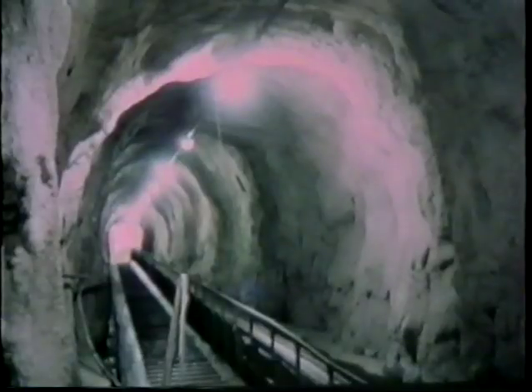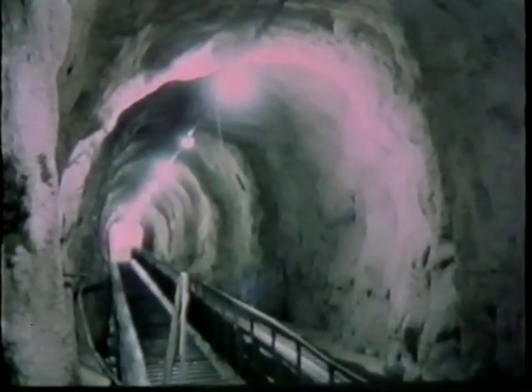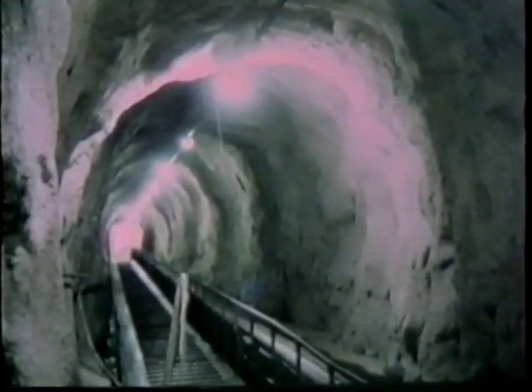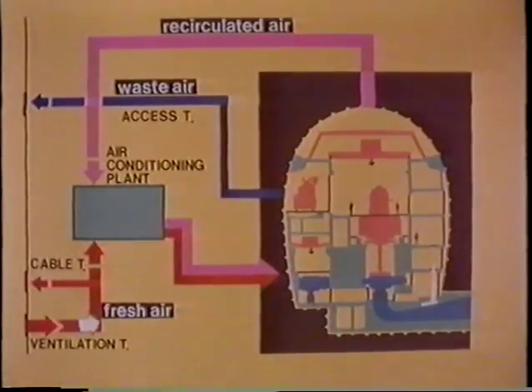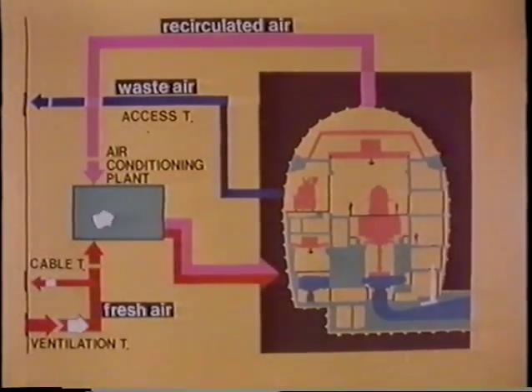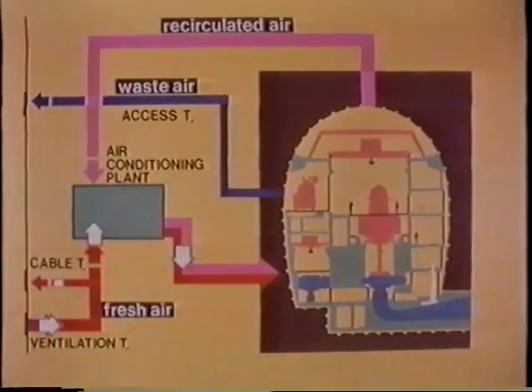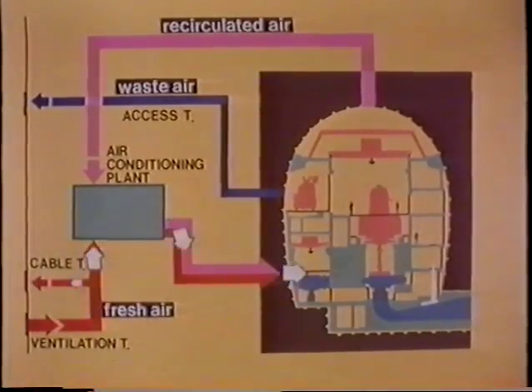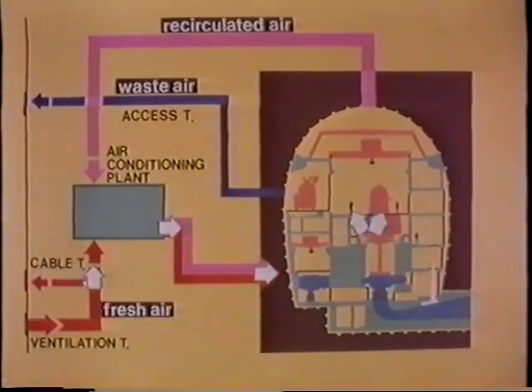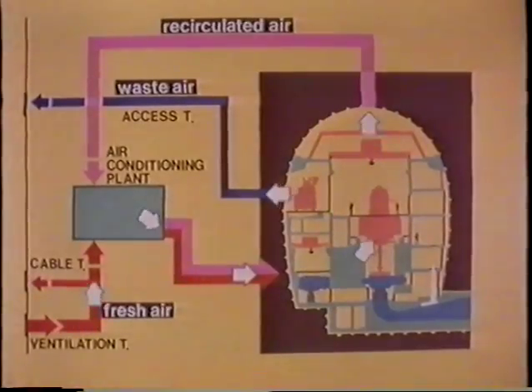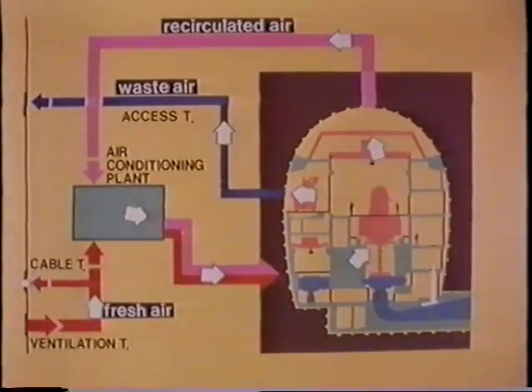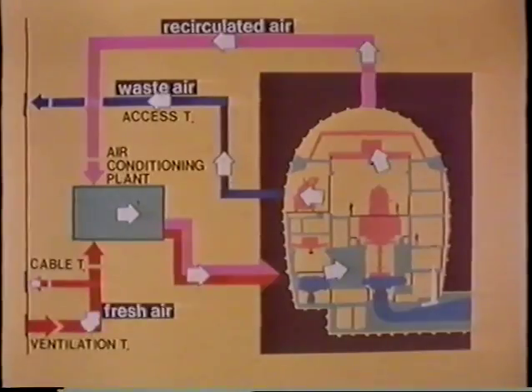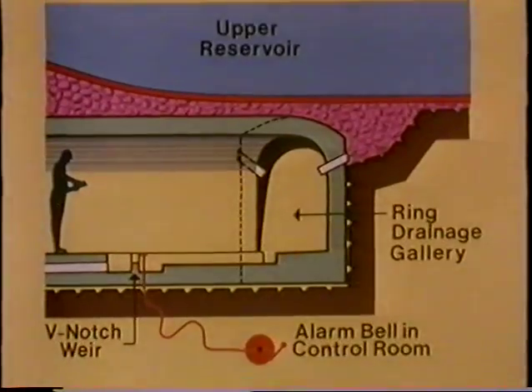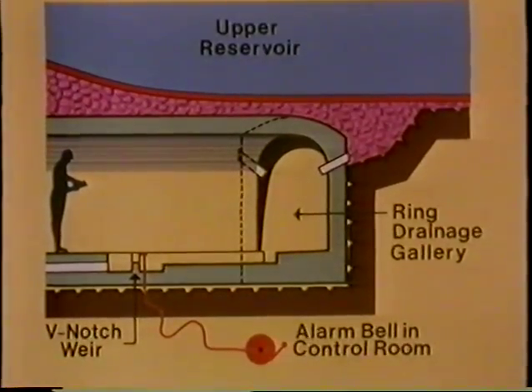In the total operation, consideration has to be given to the safety and comfort of the operations staff. An escape route for the operators is afforded by the ventilation tunnel at a high level in the cavern. In the event of fire, the ventilation is regulated to provide a straight-through system. For the comfort of the operators, the ventilation system is air-conditioned. The danger of flooding is very remote.